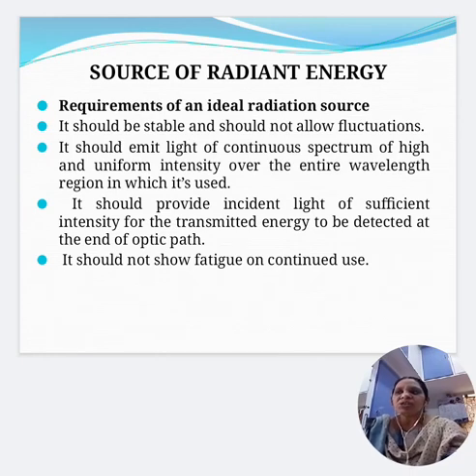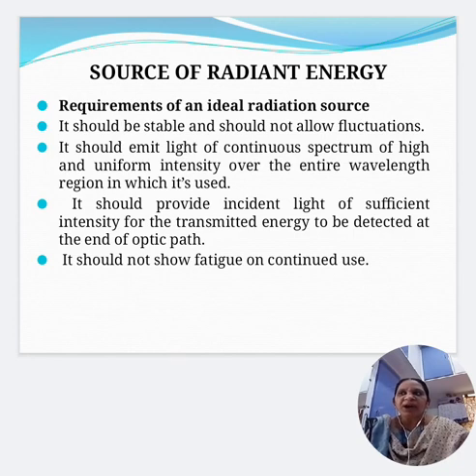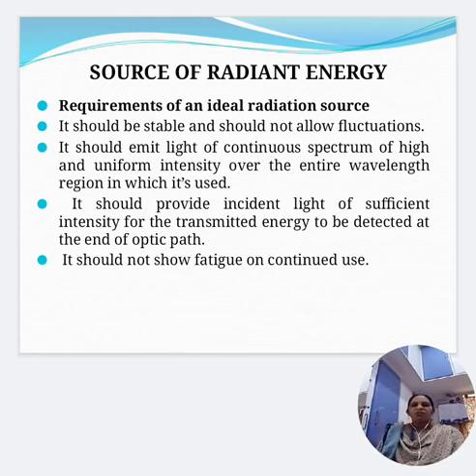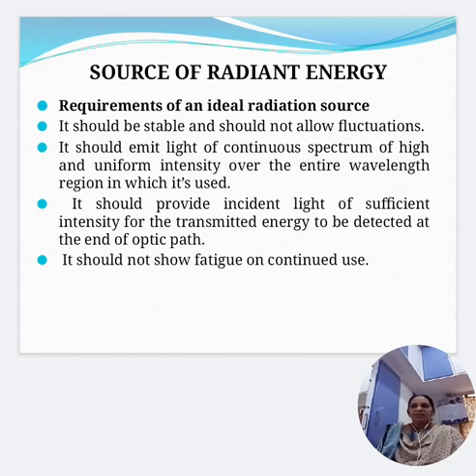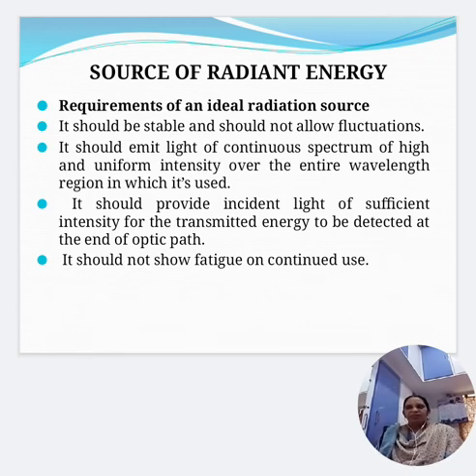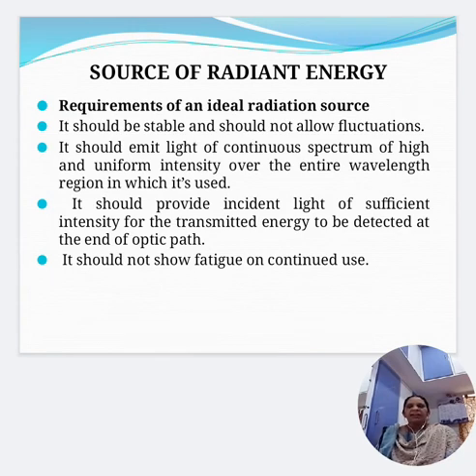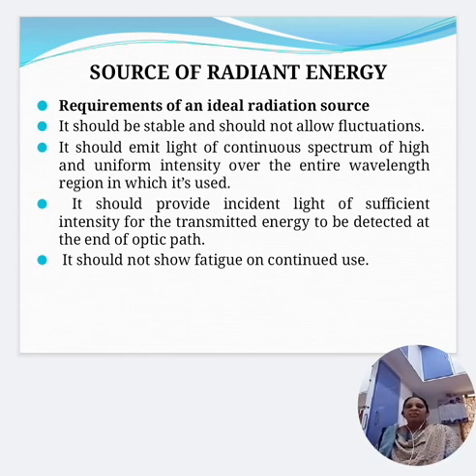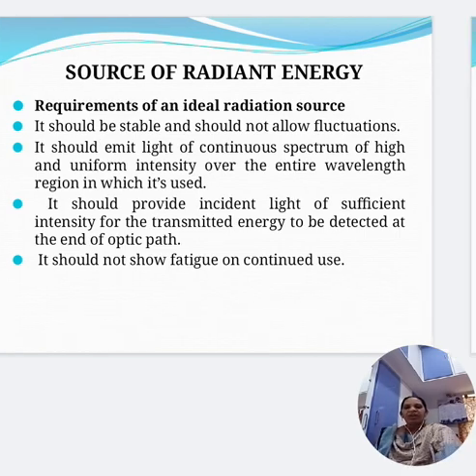The source of radiant energy: the basic requirements of an ideal radiation source are that it should be stable and not allow fluctuations; it should emit light of continuous spectrum of high and uniform intensity over the entire wavelength region in which it is used; it should provide incident light of sufficient intensity for the transmitted energy to be detected at the end of the optical path; and it should not show fatigue on continued use.